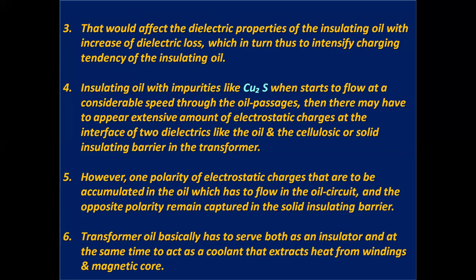Number four, when insulating oil with impurities like cuprous sulfide starts to flow at a considerable speed through the oil passages, an extensive amount of electrostatic charges appears at the interface of two dielectrics, like the oil and the cellulosic or solid insulating barriers in the transformer. One polarity of the electrostatic charges accumulates in the oil flowing in the oil circuit, and the opposite polarity remains captured in the solid insulating barrier. Transformer oil serves both as an insulator and as a coolant that extracts heat from the windings and magnetic core.